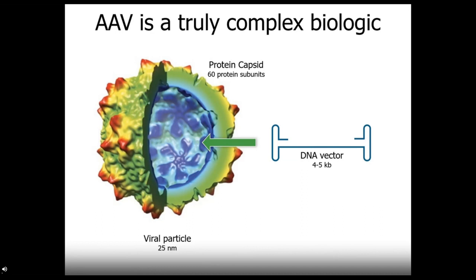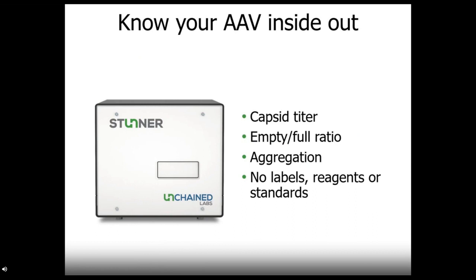We already mentioned turbidity quantification. Where turbidity is normally a massive problem for a lot of UVVIS instruments, Stunner is able to understand turbidity and analyze it to tell you a bit more information what is going on with your particle. Here we are looking at turbidity signal from a two times dilution series of empty LNPs. You can see that as a sample gets diluted every step, the turbidity also decreases. And it turns out that decrease is very linear. What we are doing here is taking a sample of empty or full LNPs and we measured that particle target. Then we have taken that two times dilution series and quantified it on Stunner. When Stunner quantifies turbidity, it is going to represent that as absorbance value at 260. If you plot those values against each other, you see that when you dilute these samples, you get a very linear plot. Since turbidity scales with concentration, size, and payload, you can build a standard curve against particle count and use Stunner's turbidity quantification to get a quick result on your particle count.